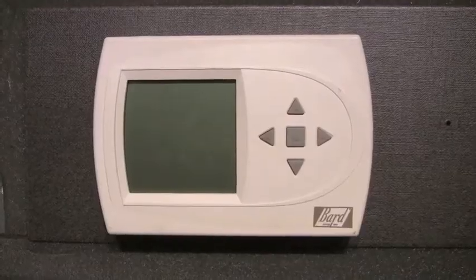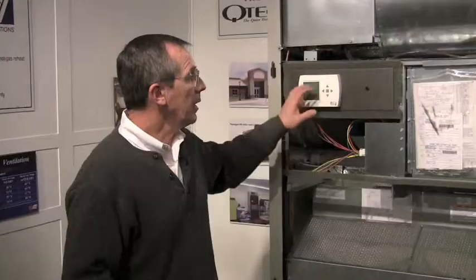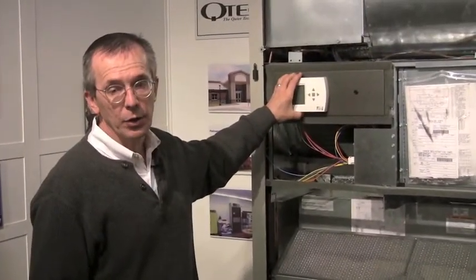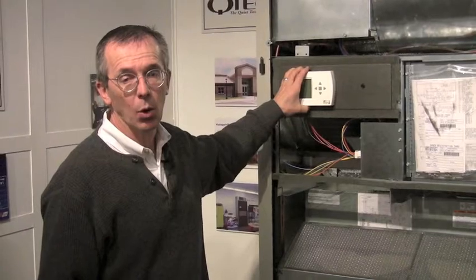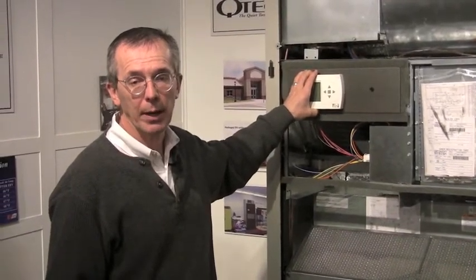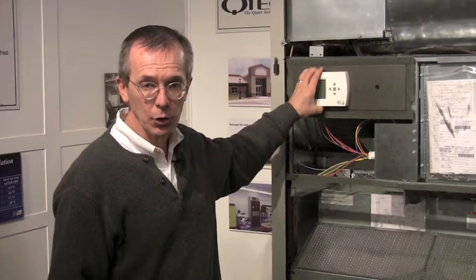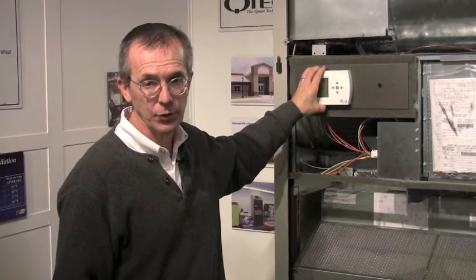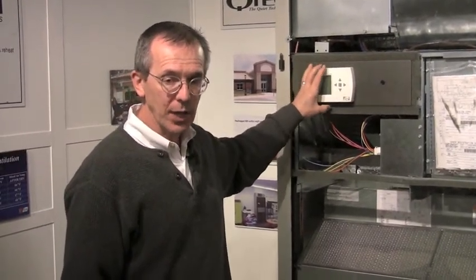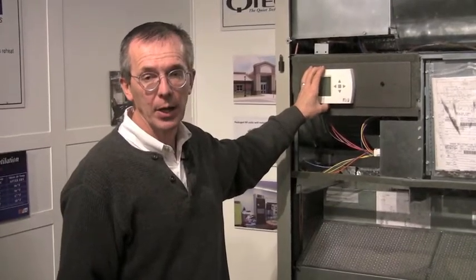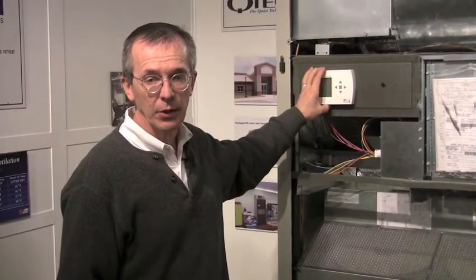As a factory installed option, Bard offers a 7-day programmable thermostat. It can be mounted to the unit from the factory the way you see it, or it can come shipped loose and you can mount it on the wall coming into the classroom or wherever it should be mounted in the classroom. It's not just a 7-day programmable thermostat, it's also a combination humidistat, particularly if the unit comes with hot gas dehumidification or hot gas reheat. This particular unit here has hot gas reheat for dehumidification.